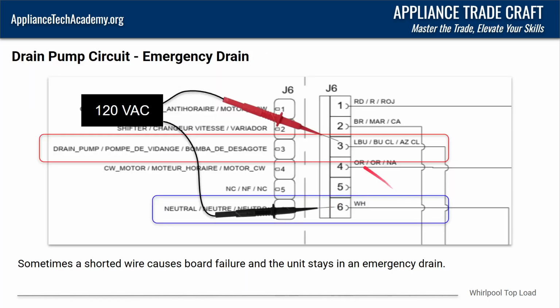But, yeah. So, one other thing to keep in mind when you are out on one of these calls, if the unit is in an emergency drain, what I like to do is disconnect the pressure tube from the control board, unplug the unit from the wall for maybe 10-20 seconds, put my meter leads, put the J6 connector back in, back probe the light blue wire and the white wire for AC voltage, leave the pressure tube disconnected, plug the unit back in. If you're getting 120 volts with the pressure tube disconnected, the control board has likely failed.